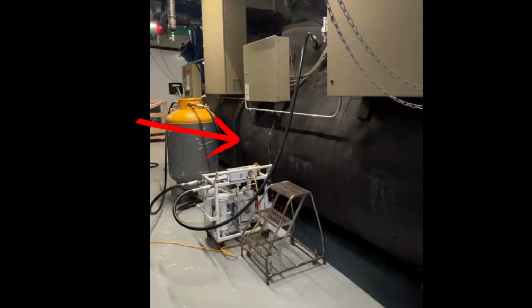And then essentially what's happening is there is a lower pressure on this cylinder than the refrigerant pressure of the evaporator, which causes a draw into the cylinder. At the same time, we're maintaining a pressure on the evaporator by pushing that vapor back into the chiller, and it creates this self-looping process where as we're pulling here, we're pushing back here, and this liquid refrigerant charge is getting drawn out of the chiller and into the recovery cylinder. And as this is happening, no liquid refrigerant is flowing through our recovery machine.